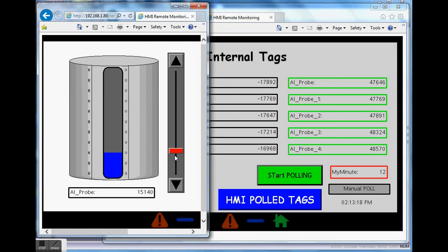So I'm just using that function right now, the GetNow, based on what time, to have this poll. You could also have this be based on the hourly poll, and so forth. So it's a pretty cool function to have it just go out and automatically grab data. In this case, once an hour, and it's going to grab it for 1 minute, and then after that minute, it's done. So if you have a variable or some kind of tank thing that doesn't change that much, to be honest with you guys, if you're polling it for 1 minute, it's not going to change dramatically. It's perfectly fine to have this run for 1 minute.